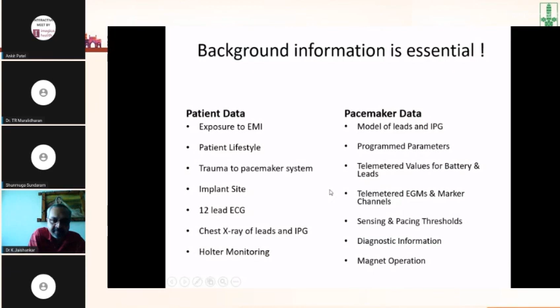As regards pacemaker data, as Dr. Kayun elegantly pointed out, what is the model of the pacemaker, leads, the IPG, the program parameters, and if you have any telemetry values for battery and leads from the EGM and Marker channels, sensing and pacing thresholds, diagnostic information if any, and if a magnet has been applied on top of the pacemaker. Next, please.